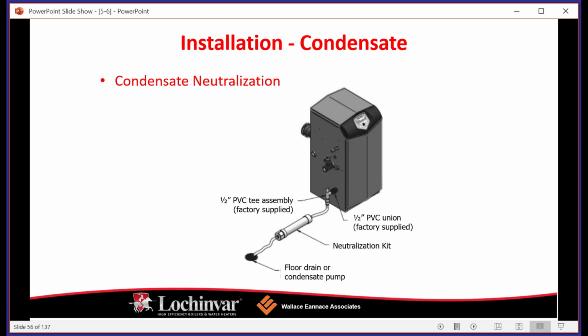Very important that we handle that condensate correctly. You're going to see the third bullet point here. Larger units use larger neutralization kits, right? Every single condensing boiler that we install, whether it's code or not, is going to want to use a neutralization kit, okay? So here's a good slide that shows exactly how this gets laid out.